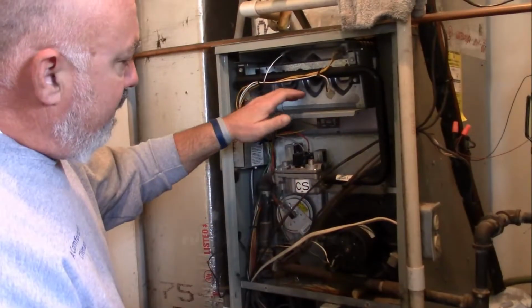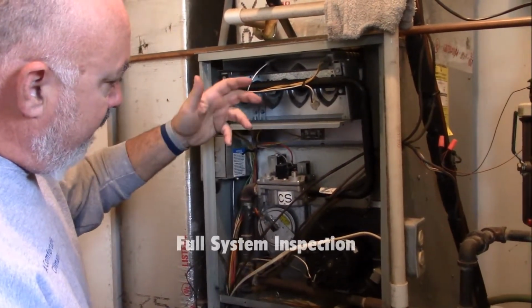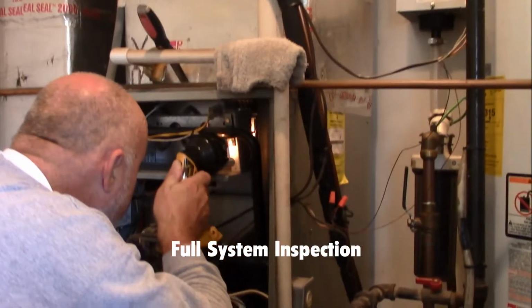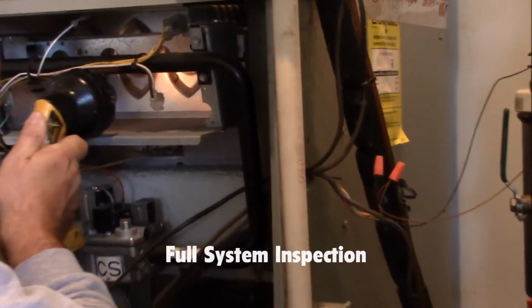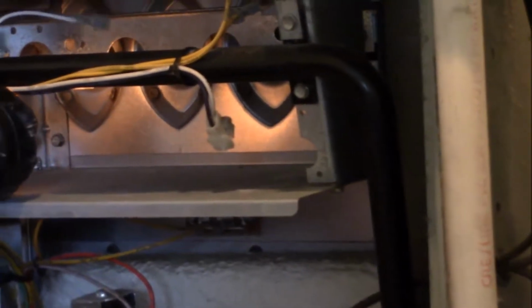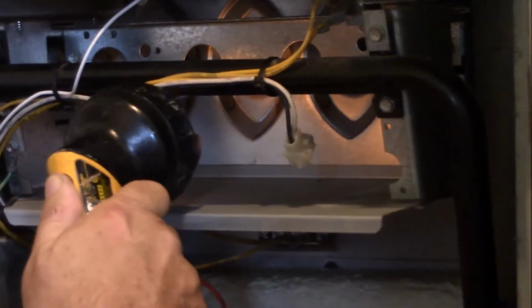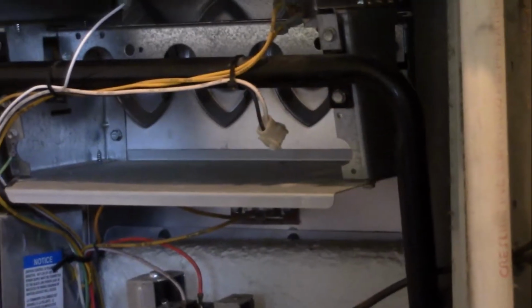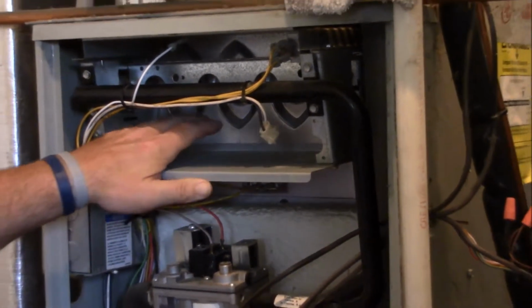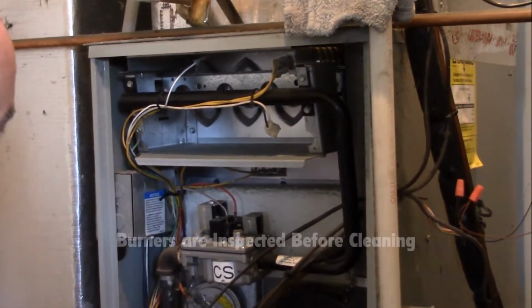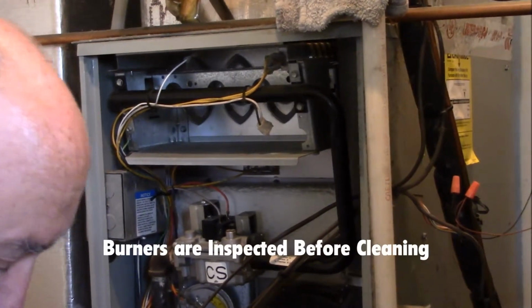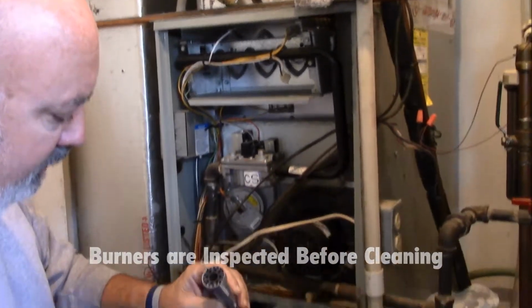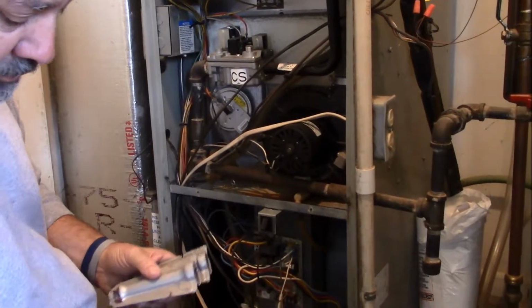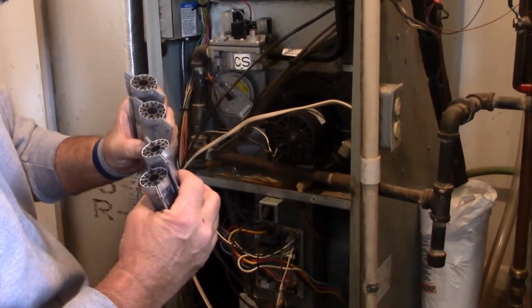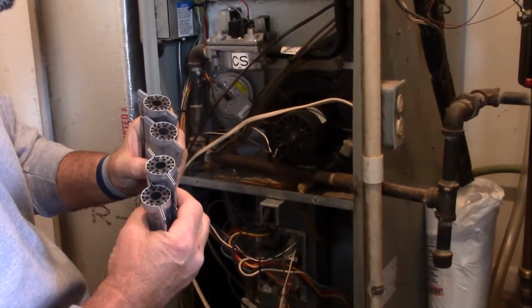The burners have been removed. I'm now going to visually inspect everything and give everything a good looking over. I don't see any signs of any rust or corrosion in this furnace. Heat exchanger seams look tight at the top. Again, the heat exchanger didn't put out any carbon monoxide, and the visual inspection of it here, we can see what's going on with that limited view. It still looks okay. These are the burners that are taken out. They're visually inspected for rust and corrosion to make sure that they can still perform their duty properly. They'll be washed out in a sink and dried and reinstalled.